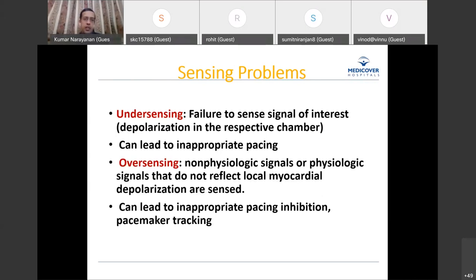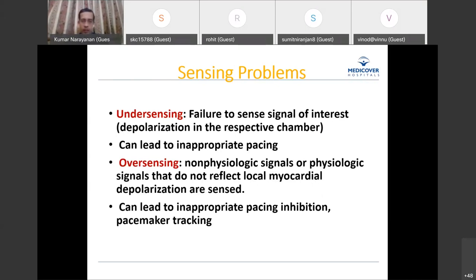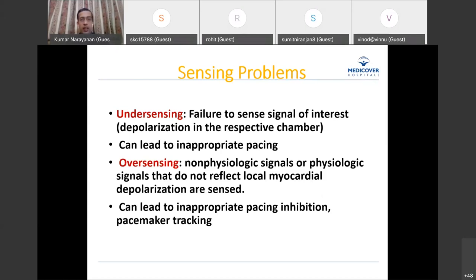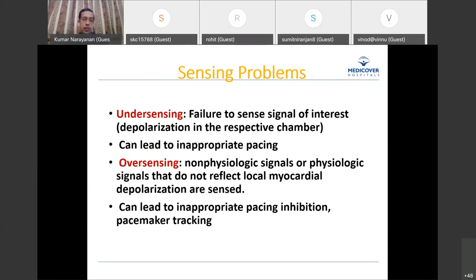Under-sensing means the pacemaker is failing to sense the signal of interest — the depolarization in the respective chamber — causing inappropriate pacing. Over-sensing means the pacemaker falsely reads a depolarization in a chamber because of other signals such as myopotentials, electromagnetic interference, or physiologic events like T waves and far-field R waves. Over-sensing leads to inappropriate pacing inhibition and, in dual chamber pacemakers, problems with tracking sensed events.